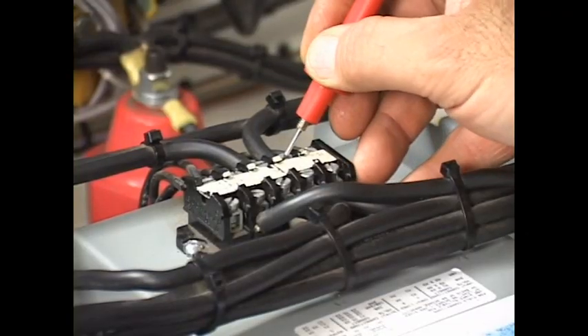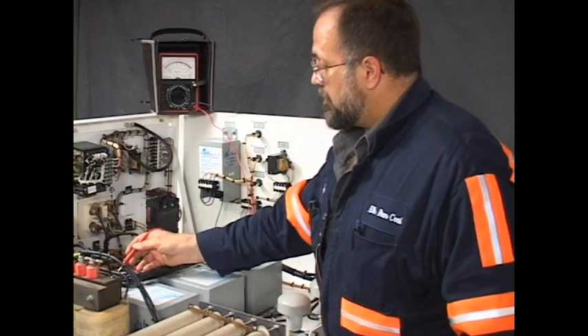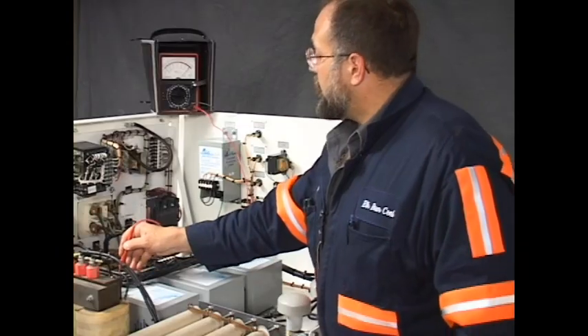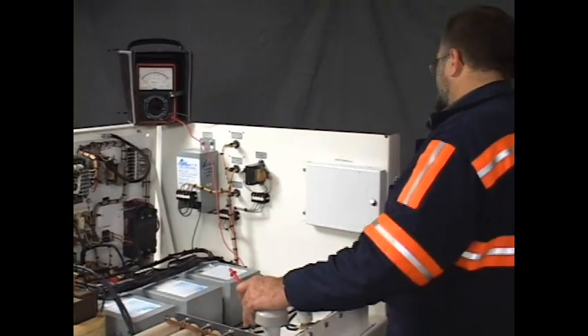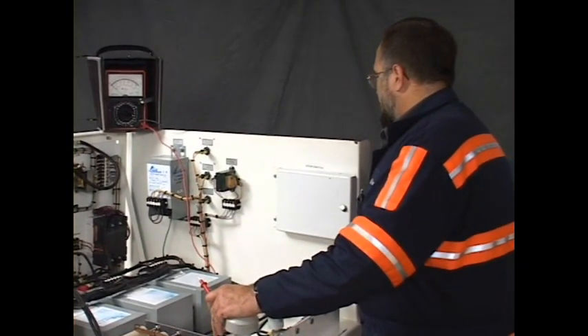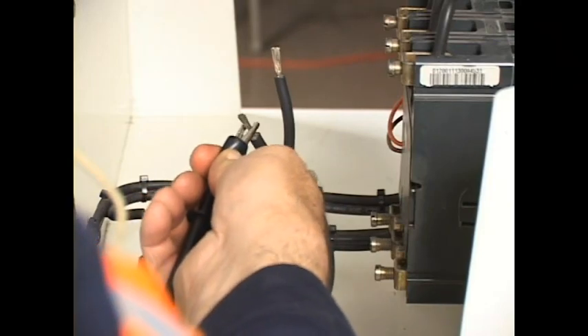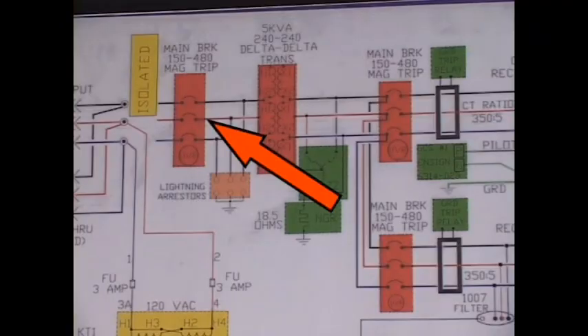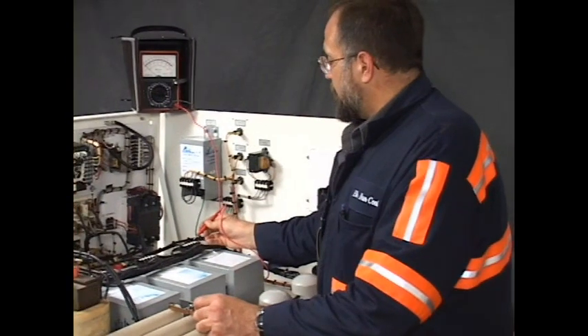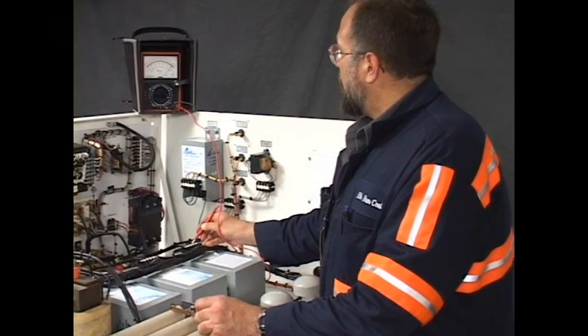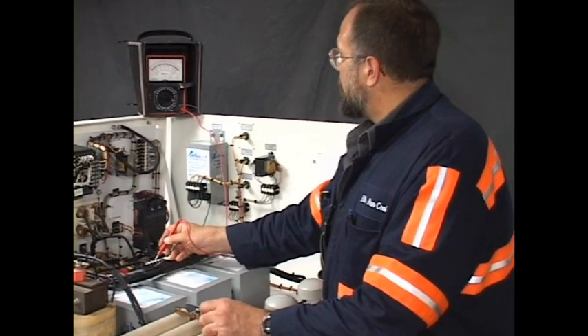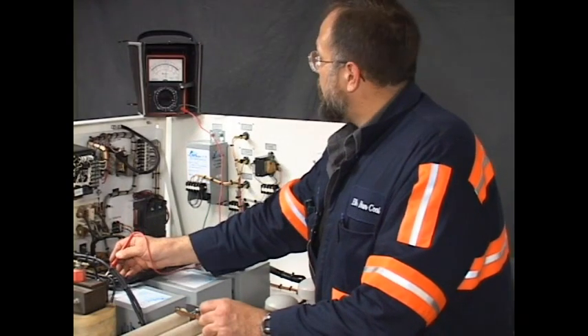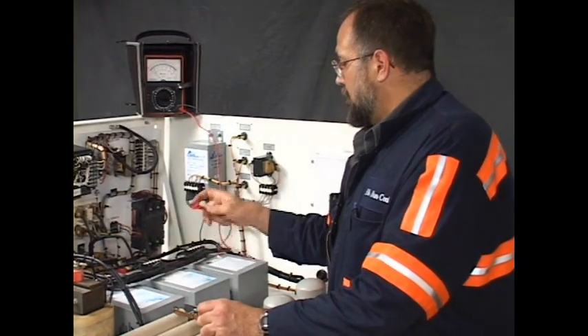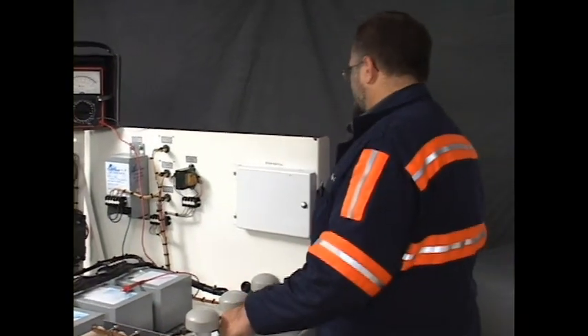Going to the second transformer, again we have continuity, and to the third transformer we have continuity. Okay, we want to say that phase is intact. Now I'm going to the second phase, which is in the middle. It's this phase here, off the bottom of the main breaker. Read to the first transformer, and we have continuity. The second one, we have continuity, and the third one, we have continuity. I can believe that phase is intact.